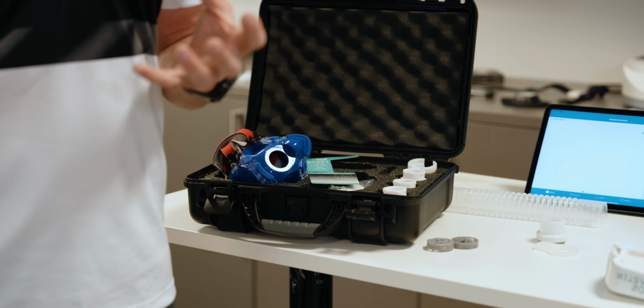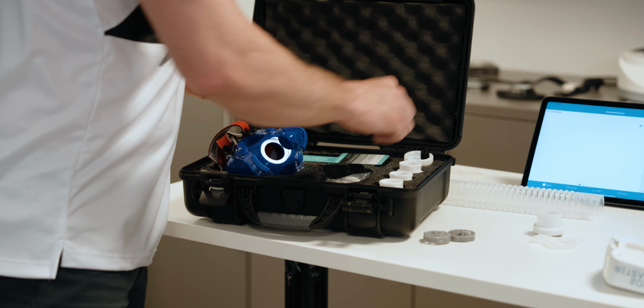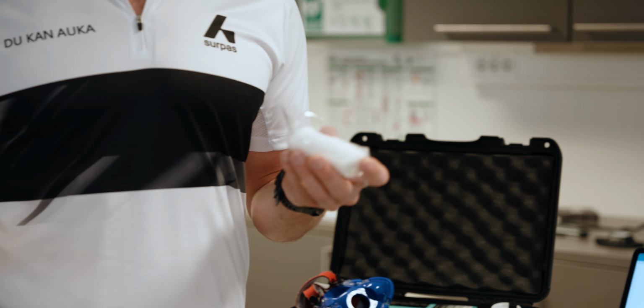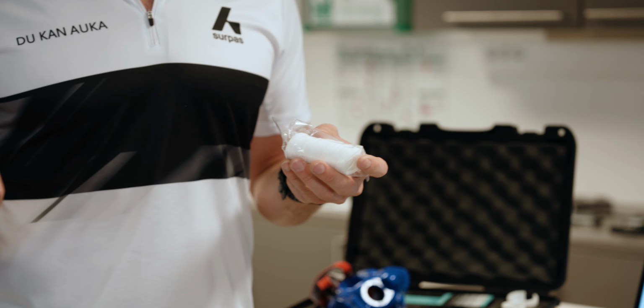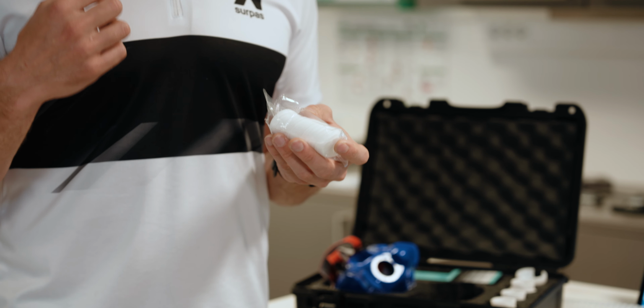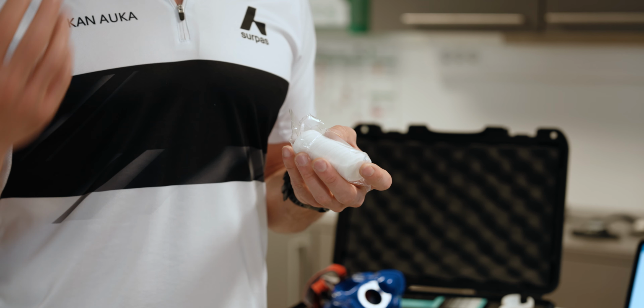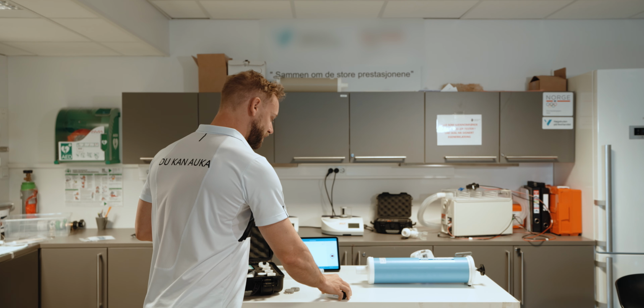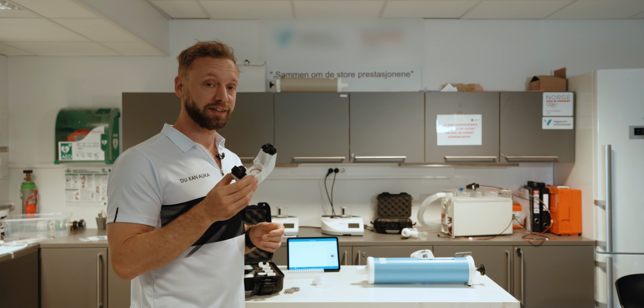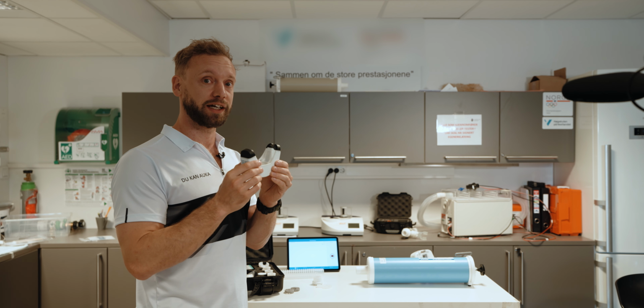The last piece you also need to remember when you assemble the units is the filters. In the standard kit, you get 50 filters, and you use 1 filter per test. This is one of the crucial things that you calibrate for when you do the flow calibration. So let's dive into the actual unit. This is the VO₂ Master, the actual analyzer.